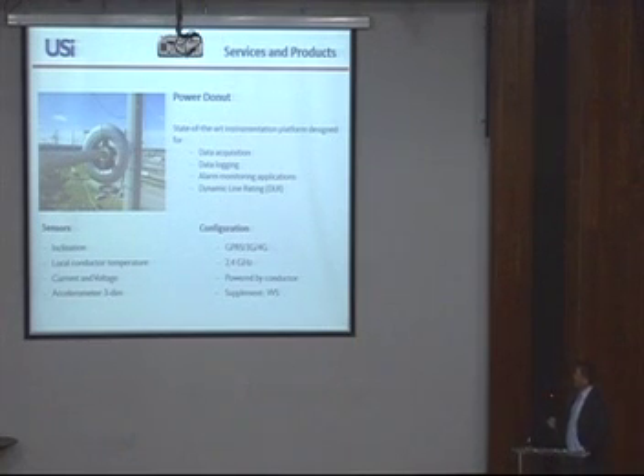The Power Donut, you have seen it before with Carlos. It's installed directly on the conductor. The new version, which has been out for 3 years, has quite a lot of sensors included in the device. I talked about the inclination, so it measures the angle at that point, and this angle can be used to calculate the tension and do the same procedure as with a CAT. It also has a local temperature sensor.